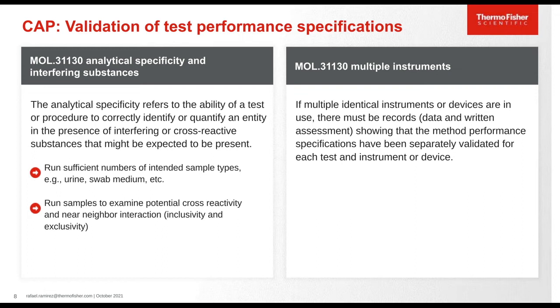Analytical specificity and interfering substances refers to the ability of a test to correctly identify or quantify an entity in the presence of interfering or cross-reactive activity of substances that might be expected to be present. Running sufficient numbers of samples of your intended sample type will help here. You want to examine potential cross-reactivity and near-neighbor interaction to establish inclusivity and exclusivity. When it comes to multiple instruments, even if they are identical, there must be records showing the exact serial number that each instrument was separately validated.